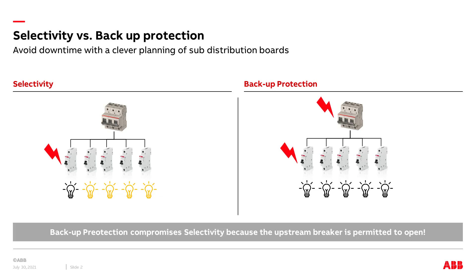In cases where the available short circuit level exceeds the short circuit rating of the downstream breakers, a current limiting upstream breaker can be used to ensure proper protection of the installation.